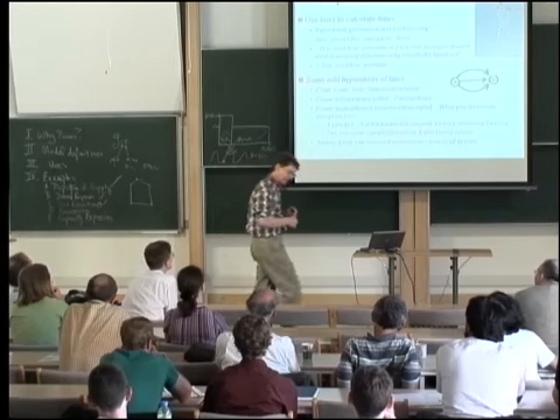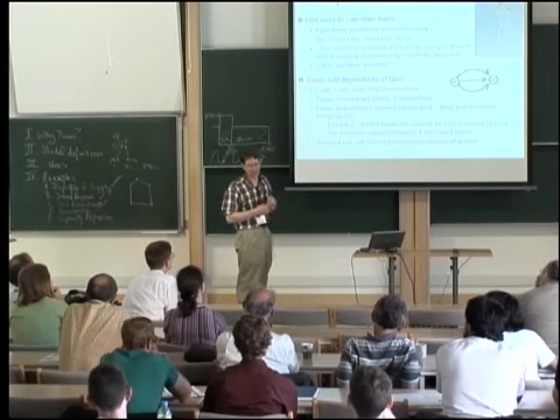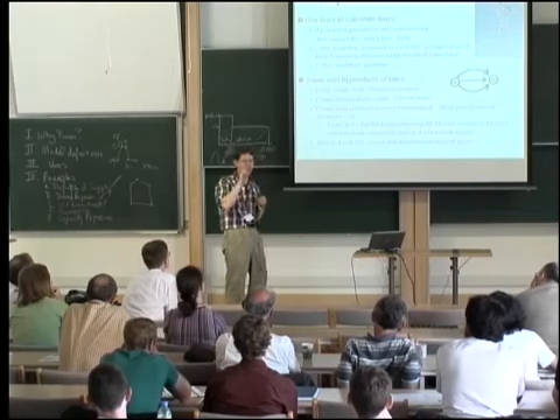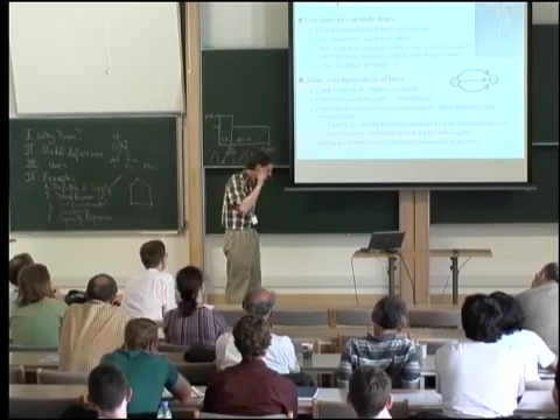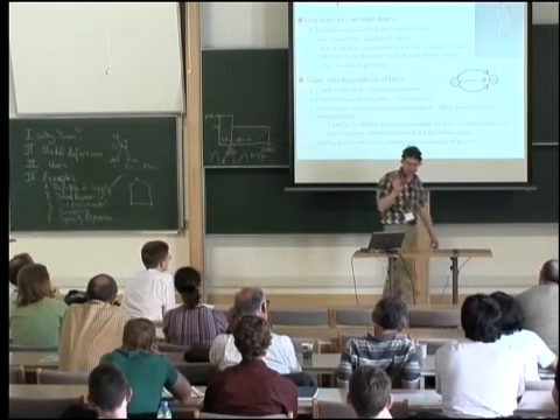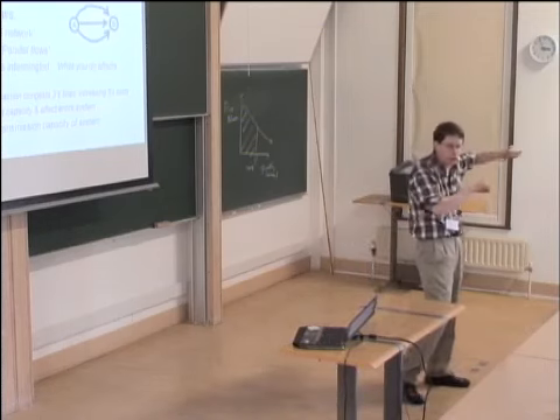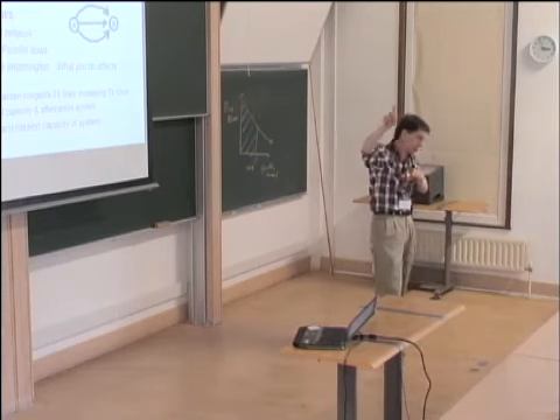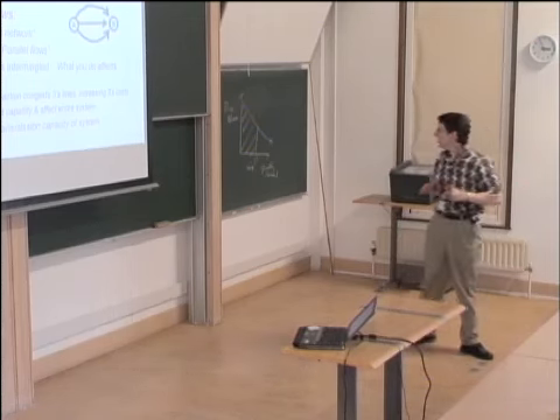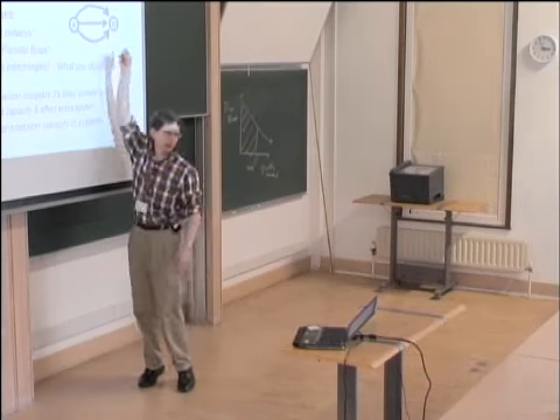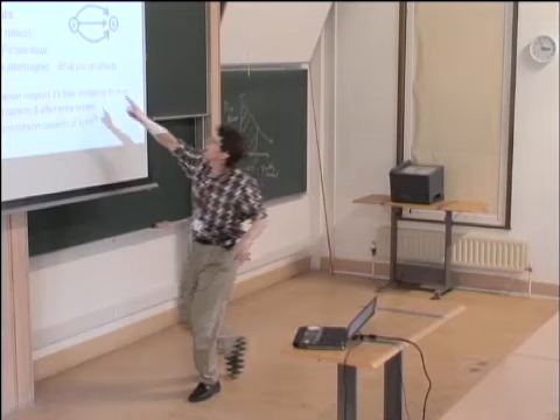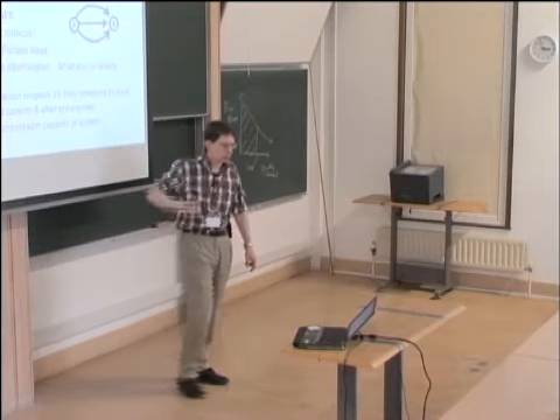No, it does—Ohm's laws and Kirchhoff's laws give a minimum of the energy losses, don't they? That's true, in terms of energy losses that's right. Energy losses are minimized by Kirchhoff's laws, but if you have capacity limitations, you can only put so much current through a line before it overheats and sags, which is what initiated the August 2003 blackout in the US. You have to worry about the capacity of the system. And if, for example, I added a fourth line but didn't bother to clear the vegetation under it, it would only be able to take a small amount of current, so you'd have to back off your generation so you don't overload that one line. But that was an excellent point.